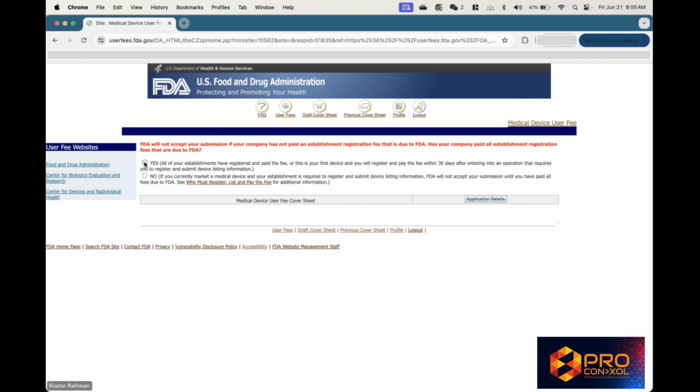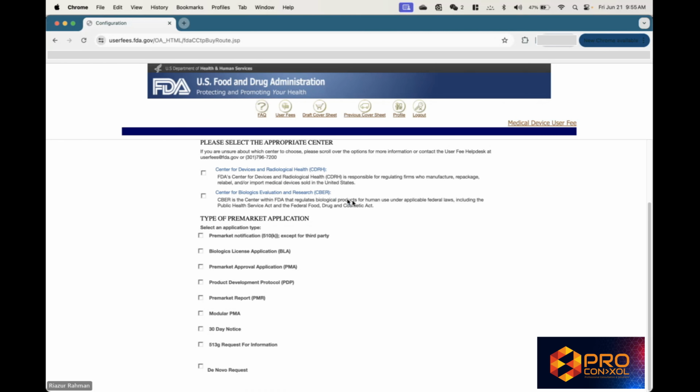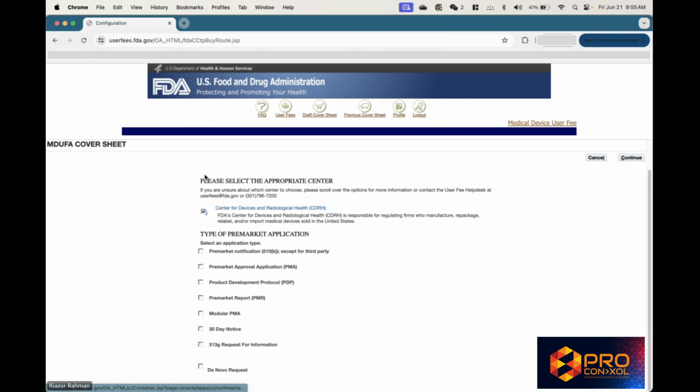Note, FDA will not accept your submission if your company has not paid an establishment registration fee that is due to FDA. In this instance, we will select Yes. Then we will click Application Details. Depending on the type of submission, you will select the appropriate center. For this video, we will select CDRH.